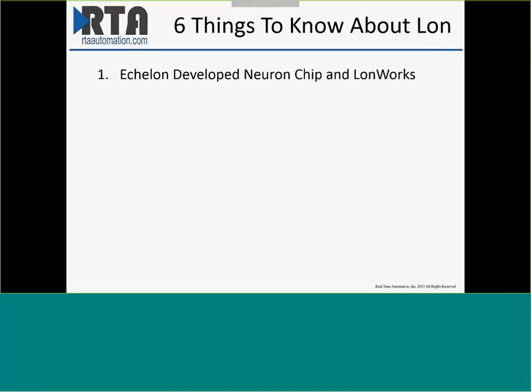There are six things you need to know about LonWorks. First, Echelon developed the neuron chip, and every LonWorks device has one. The neuron chip is the MAC — the Media Access Controller — the part of the hardware that decides when to put the next bit onto the network. It's a very sophisticated piece of hardware with three communications processors working together.